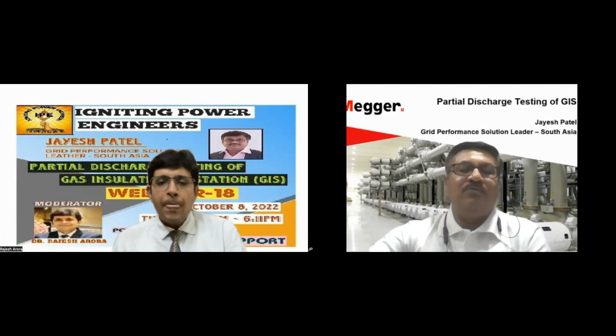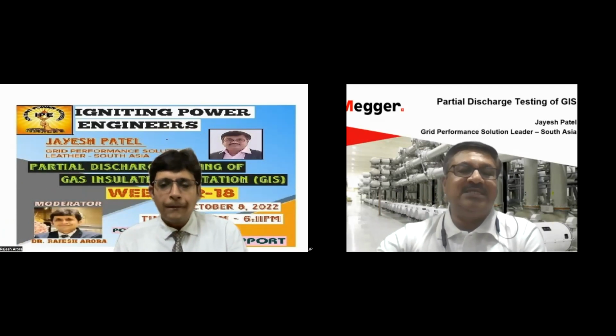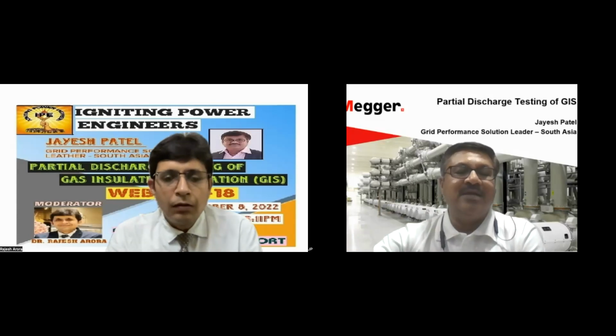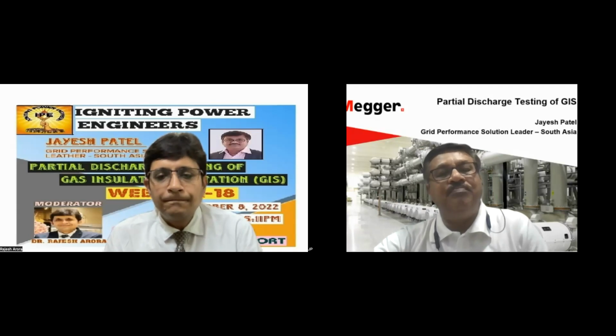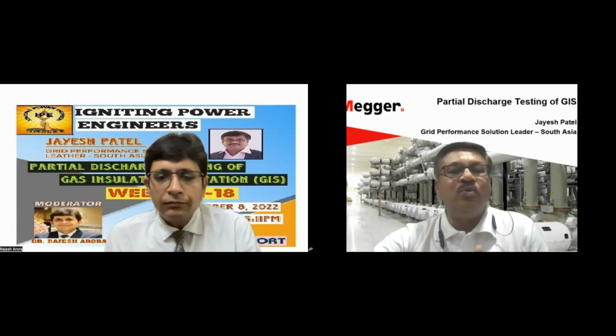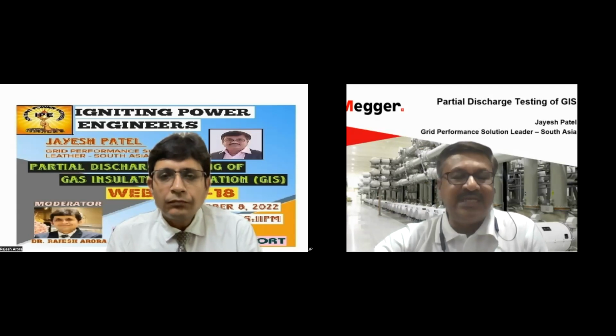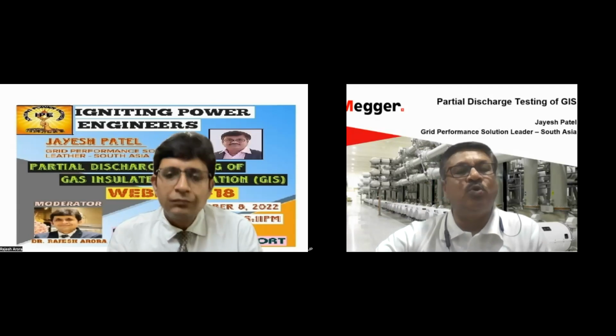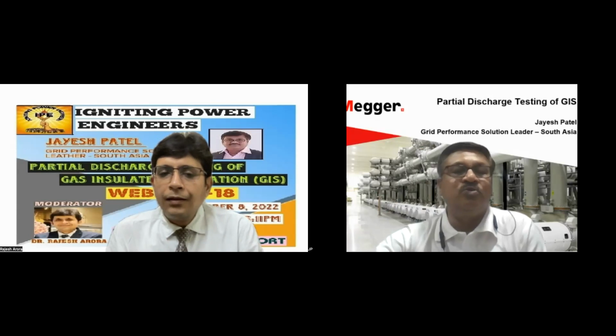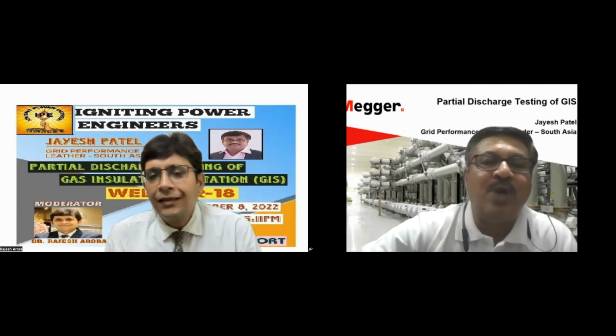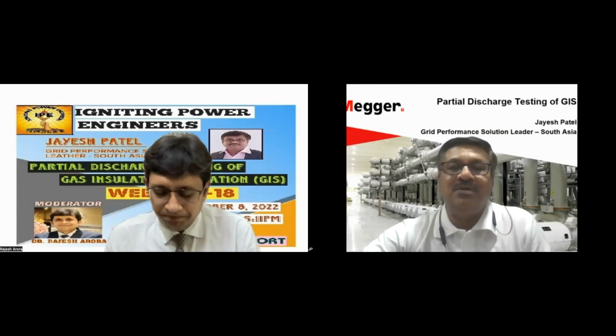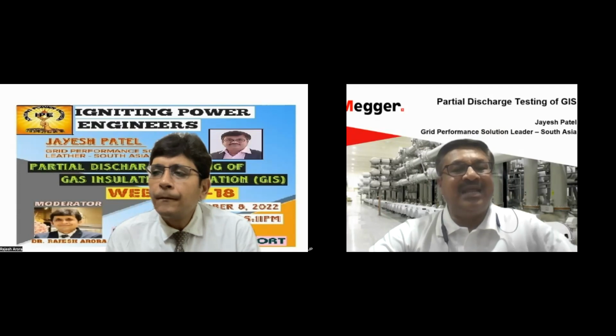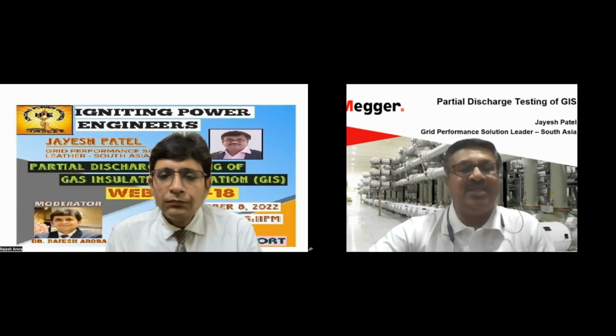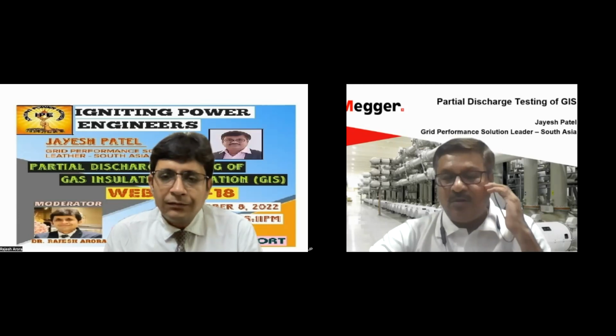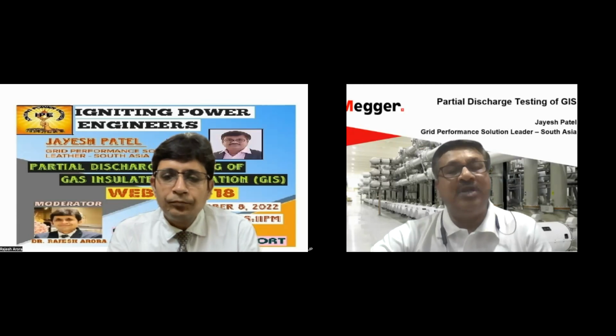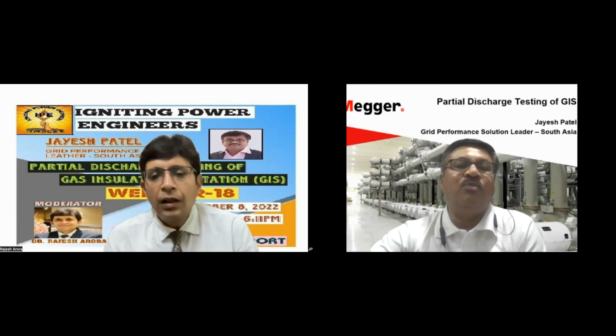Absolutely. See, we advocate a concept that if you have a budget, online is the best. But if you don't have budget, what people do is carry out the PD measurement with portable spot testing on a quarterly basis. And if you get some sensors where you are getting doubtful signatures, or if you are getting PD, then you can put only those sensors onto the monitoring and have a better call on those sensors, because PD is not something which is going to happen overnight. It is a gradual process. So some portions would be captured, and the portions which are clean you can leave out of measurement. So yes, with that limitation, we have 8 channel options available, which can be gradually extended up to 40 channels, in a portable version. So you can have that kind of monitoring still possible.